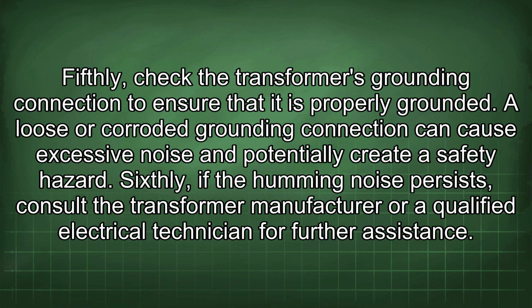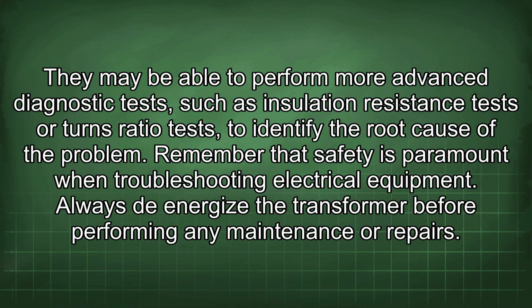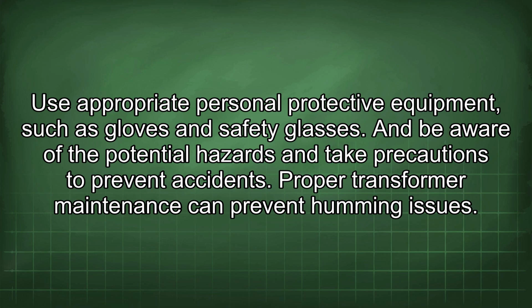Sixthly, if the humming noise persists, consult the transformer manufacturer or a qualified electrical technician for further assistance. They may be able to perform more advanced diagnostic tests such as insulation resistance tests or turns ratio tests to identify the root cause of the problem. Remember that safety is paramount when troubleshooting electrical equipment. Always de-energize the transformer before performing any maintenance or repairs. Use appropriate personal protective equipment, such as gloves and safety glasses. And be aware of the potential hazards and take precautions to prevent accidents.